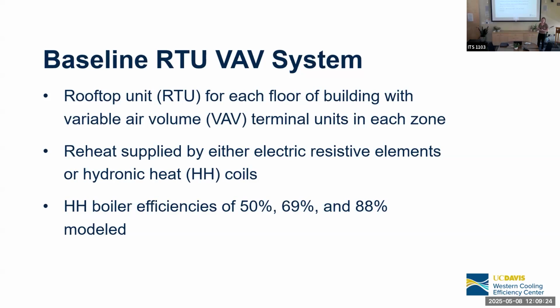So we also decided to try a hydronic heating loop, and we modeled 3 different boiler efficiencies on that loop. In the literature, it looks like while you might have a really efficient boiler, if you've got a lot of bypass happening in the reheat, you might see as low as 50% average efficiency on your boiler.